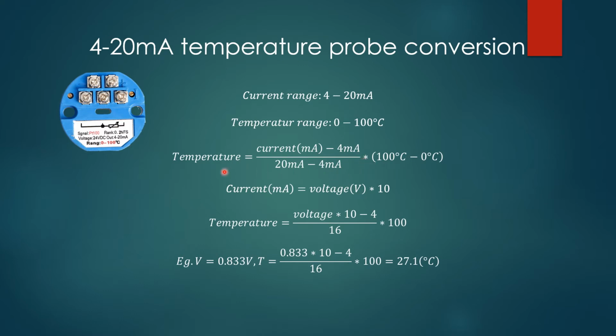You'll convert current into temperature. Okay, so how do you do it with the 4 to 20 milliamp extension board? Well, the extension board does not report current. It actually reports voltage, just for compatibility with all the high resolution analog extension boards and the analog inputs. So it reads voltages, and all you have to do is take that voltage and multiply it by 10. Once you multiply the voltage by 10, you get the current in milliamps.